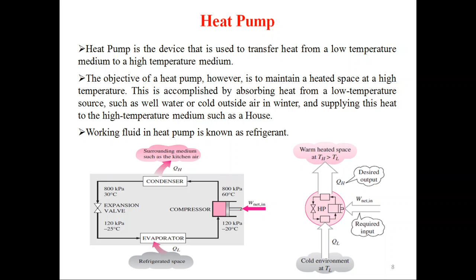Next is coefficient of performance. It is abbreviated as COP. It is the ratio of the useful desired effect to the amount of expenditure. COP is equal to the amount of cooling produced in kilowatt or kilojoule per kg in the case of refrigeration divided by the net energy supplied from an external source in kilowatt or kilojoule per kg. For a heat pump, the COP formula is the amount of heating produced in kilowatt or kilojoule per kg divided by the net energy supplied from the external source in kilowatt or kilojoule per kg. You can see in refrigeration and heat pump the denominator is the same, only the numerator changes. In refrigeration our output is cooling and in a heat pump our output is heating.